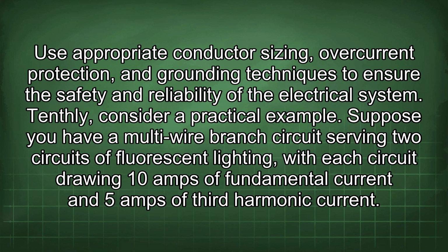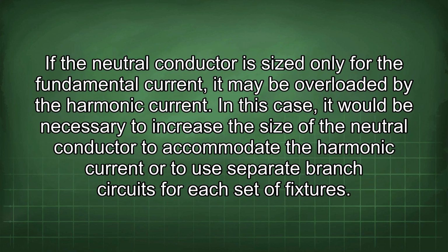Suppose you have a multi-wire branch circuit serving 2 circuits of fluorescent lighting, with each circuit drawing 10 amps of fundamental current and 5 amps of third harmonic current. If the neutral conductor is sized only for the fundamental current, it may be overloaded by the harmonic current. In this case, it would be necessary to increase the size of the neutral conductor to accommodate the harmonic current or to use separate branch circuits for each set of fixtures.